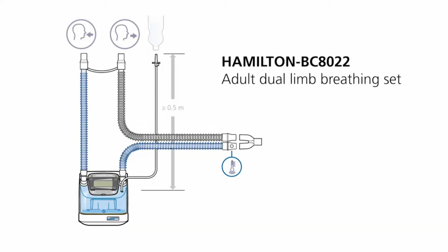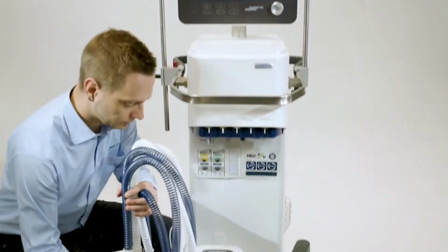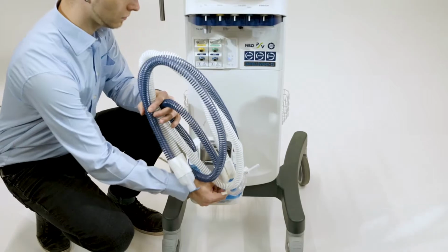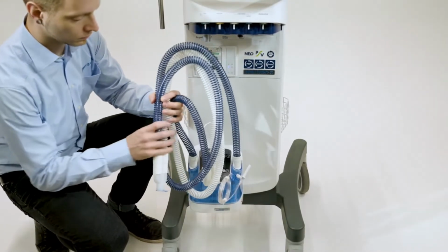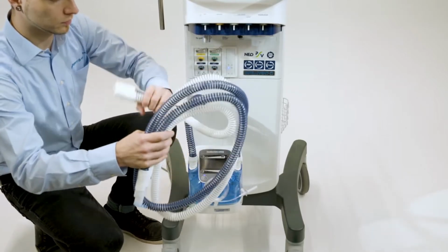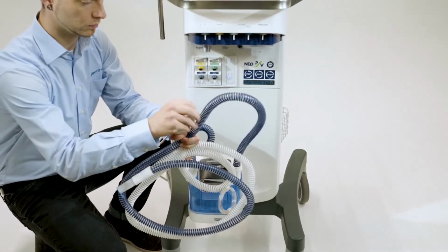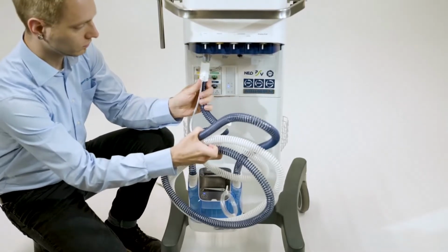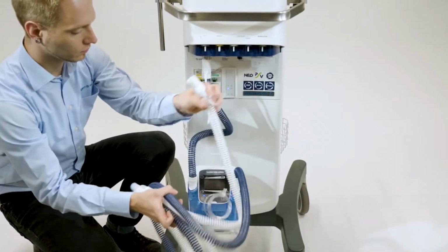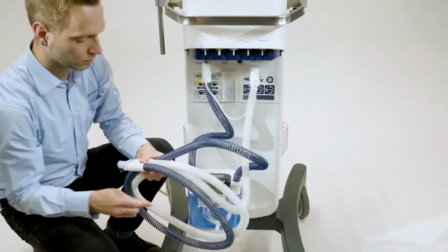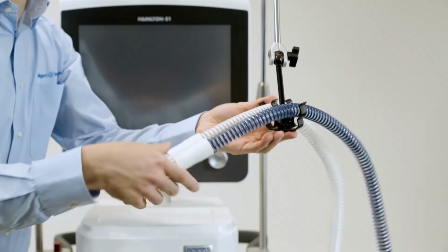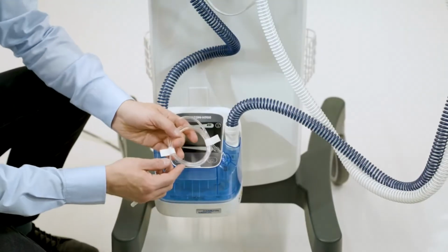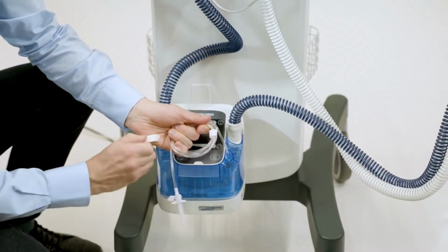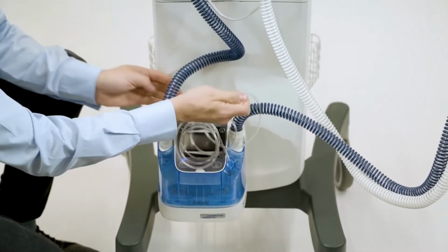The following information applies if you are using the Hamilton BC8022 breathing circuit or any other double-limb heated breathing circuit. First, insert the humidifier chamber. Connect the shorter blue tube to the inspiratory port on the ventilator. And then connect the expiratory tube to the expiratory valve. Insert the water feed line into the water bag or bottle.